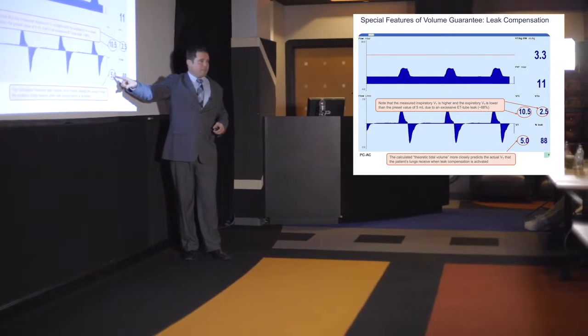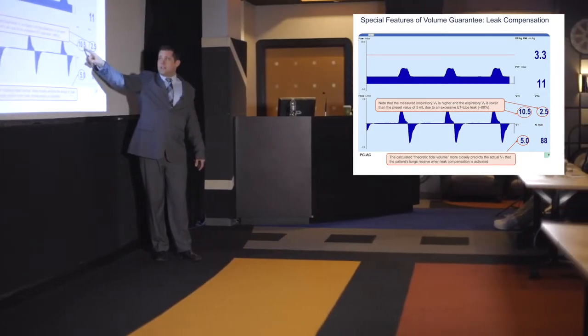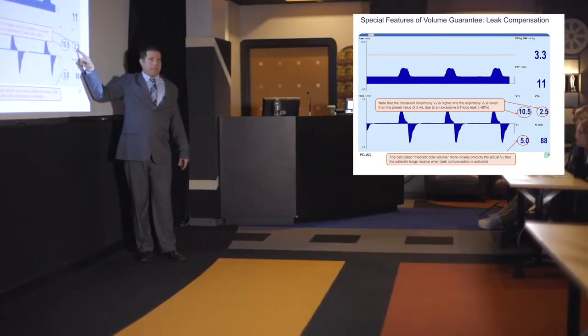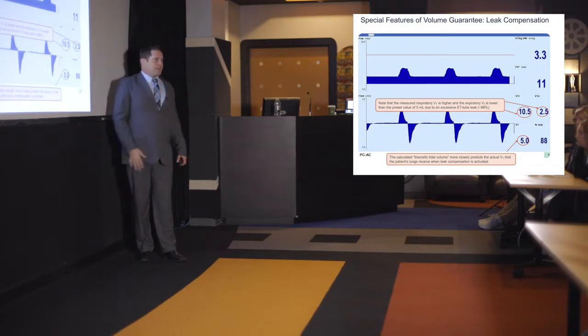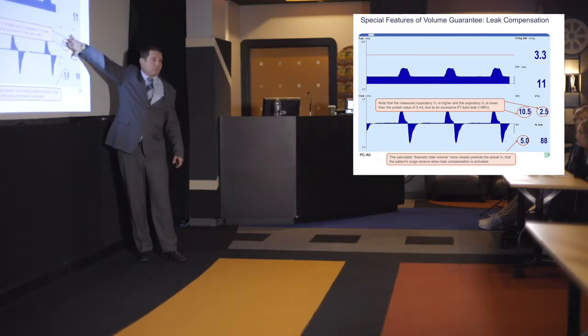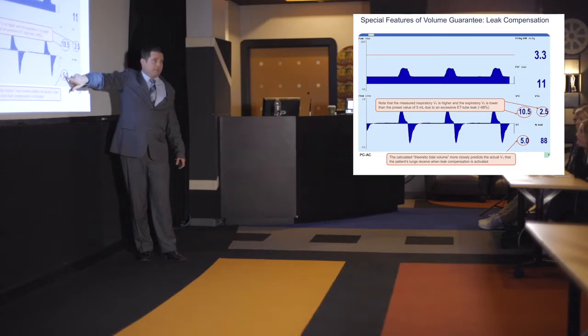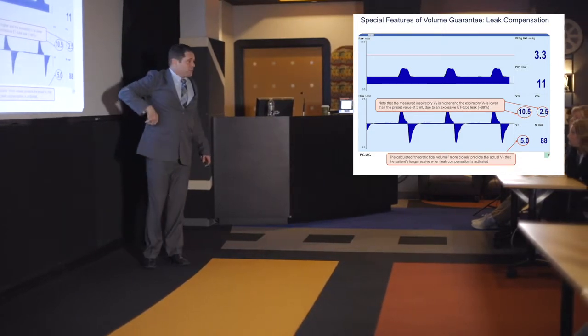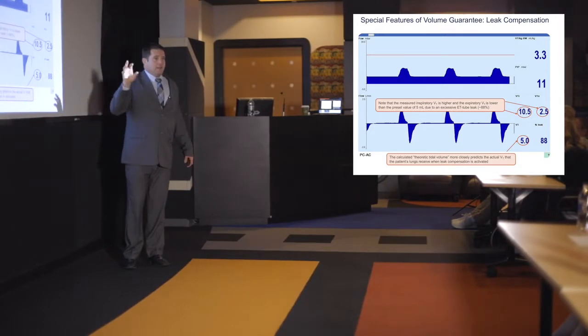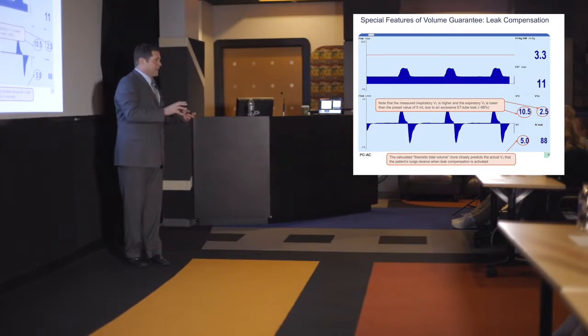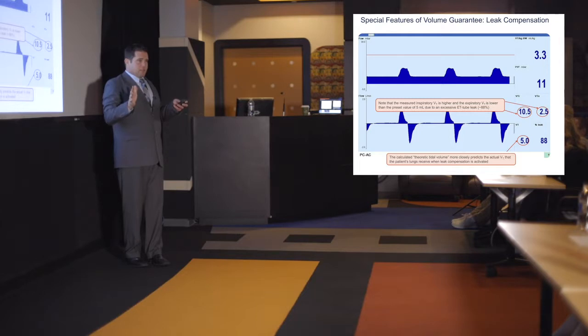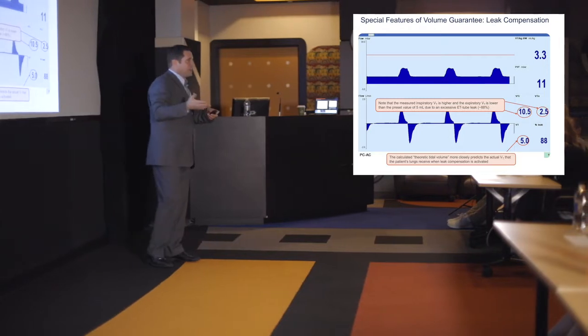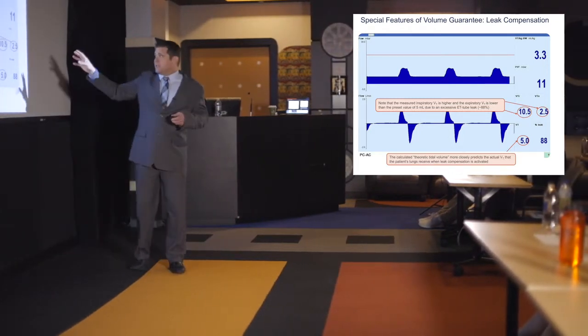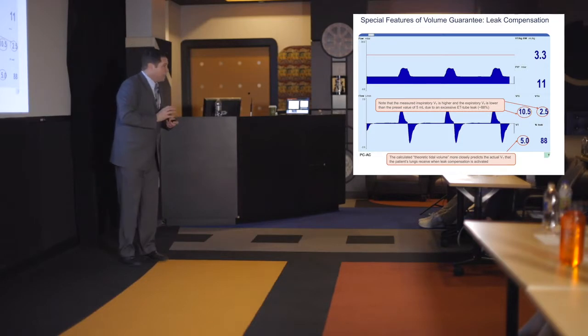When you set a tidal volume, and I don't have the settings on here, let's say we set it at 5. The ventilator is going to give 10.5. The expiratory tidal volume is going to be 2.5. How can that be? Don't even put those on your ventilator. Put the absolute volume that it thinks it's delivering. So in this particular ventilator that we use at our institution, it's going to target a theoretic tidal volume based on a leak calculation. We always think of leak compensation on exhalation, but in this case, leak compensation is occurring during inhalation as well.